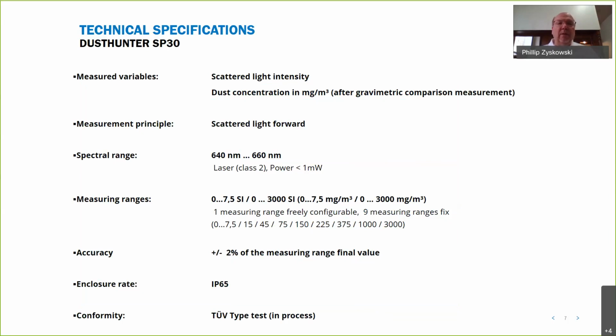What's significant here, and we'll get into each of these a little bit in the following slides, but for you to realize this is a scattered light device, and in particular forward scatter. We'll get into what that means in a minute. The spectral range isn't as important. It just tells you the laser power and the laser operating spectrum. And measuring range is very significant, and that's what makes this monitor very versatile. So we go from 0 milligrams per cubic meter all the way up to 3,000 milligrams per cubic meter. So it's a very extensive measuring range and gives us the versatility.